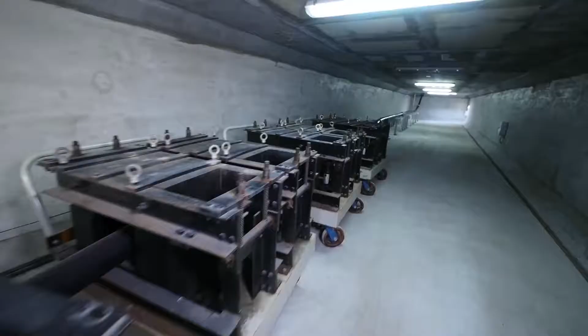In EHV accessory plant, they produce various types of joint and termination, and the plant is organized with accessory production factory, shield room, and PQ test site. The major products of EHV accessory plant are outdoor termination, which connects overhead conductors to underground cables, GIS termination, which connects underground cables to GIS system, as well as PMJ, PJ, and TJ, which are capable up to 500 kilovoltage grade, connecting various types of cables together.